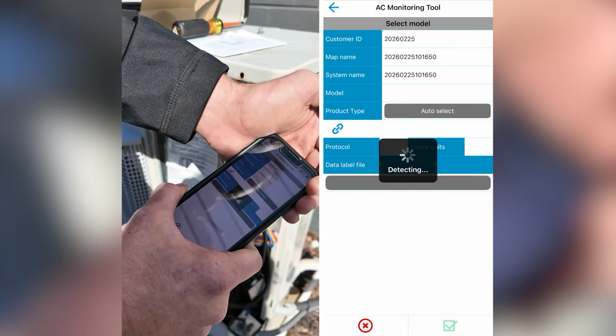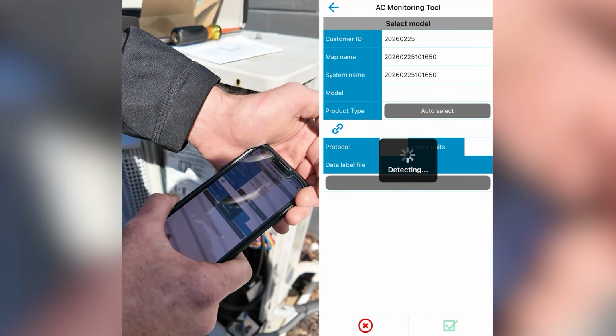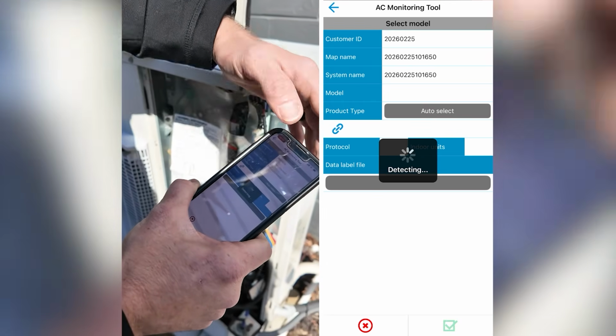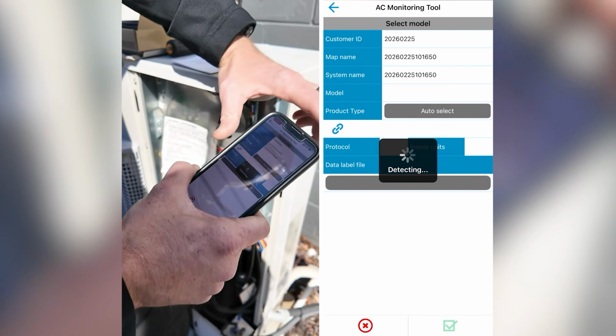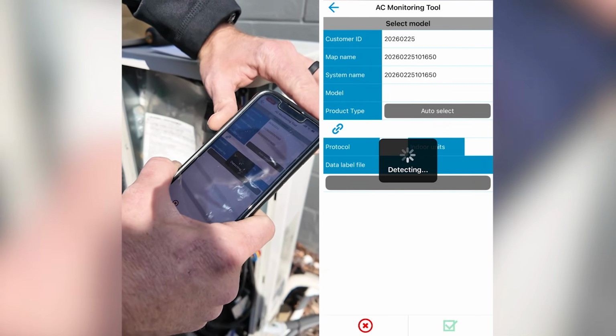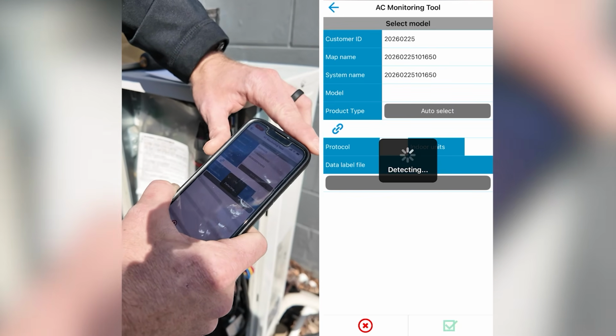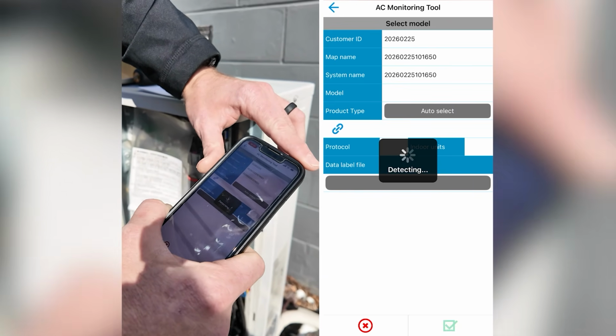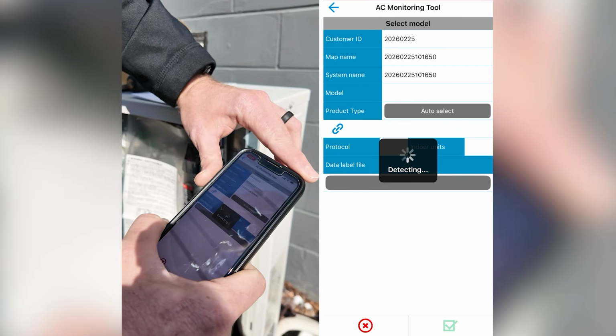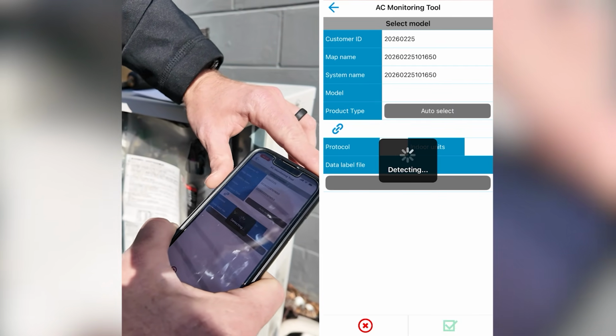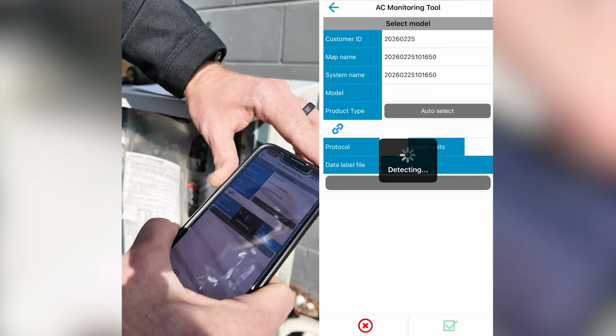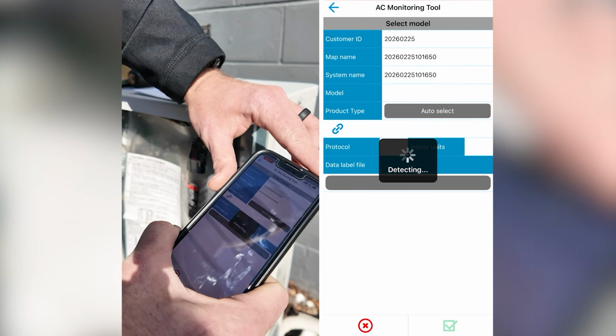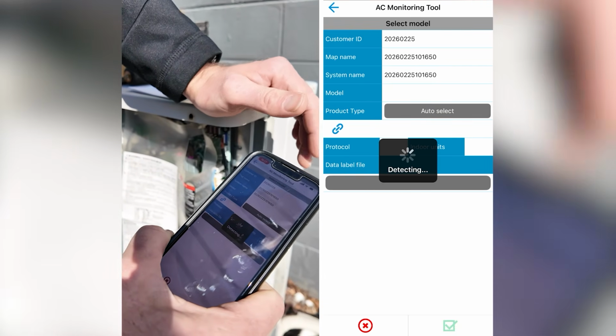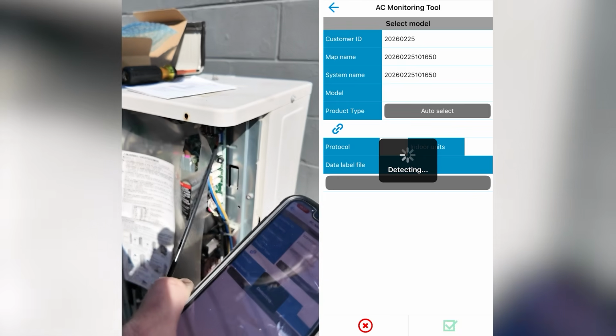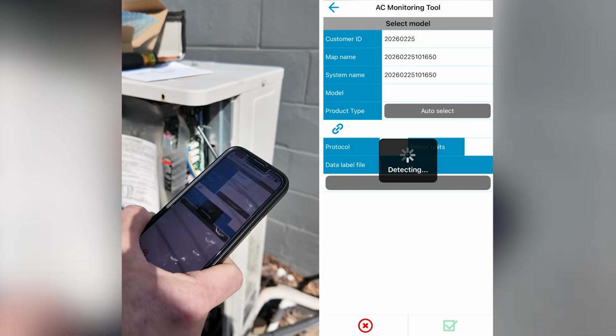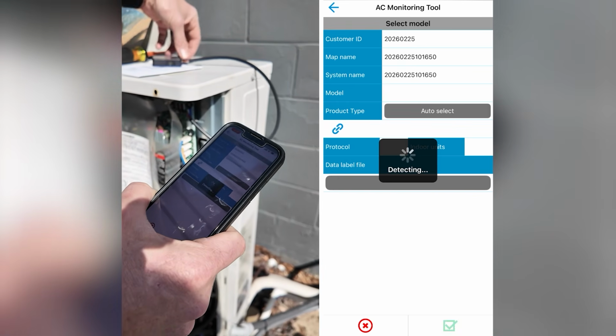Is this Altherma, which is not in our market? Is it VRV? Is it a mini split? It's going to go through and determine that. It's also going to see if it can find the indoor unit and the outdoor unit so we can pull in all the information. Now this takes as long as it takes. Sometimes if there are more indoor units connected than just one-to-one, if it's a multi-port mini split or VRV, this could take up to 5 minutes. You'll notice too that sometimes it likes to disconnect and reconnect. So sometimes keeping an eye on that red status light is also useful.